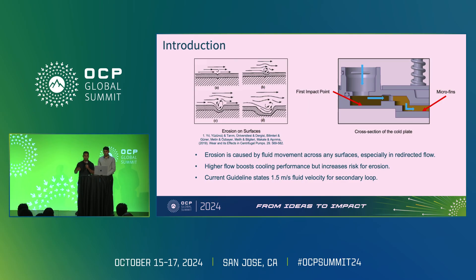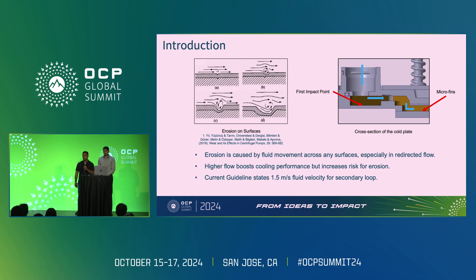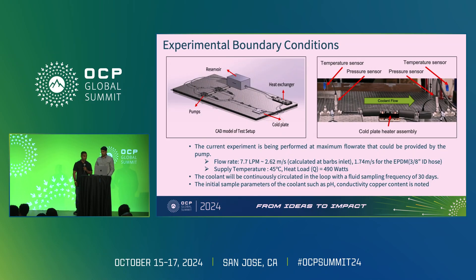Just to give a brief background on erosion and our interest in erosion: as some of you probably know, there is a current ASHRAE guidance on 1.5 meters per second fluid velocity. The hope is that if we can go to a slightly higher fluid velocity, we can improve cooling performance, but the risks associated with that would be things like erosion. At a basic level, erosion is caused by fluid movement across any surfaces, and this is obviously a concern in areas like the cold plate, but also on the secondary piping. Lo-Chan is going to go through some of the details on the study and also some of the results.